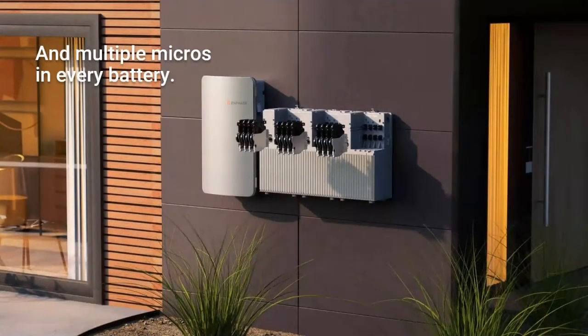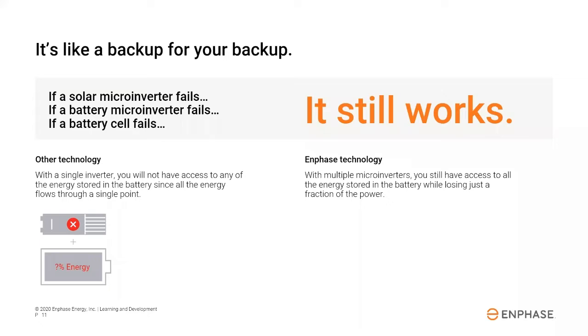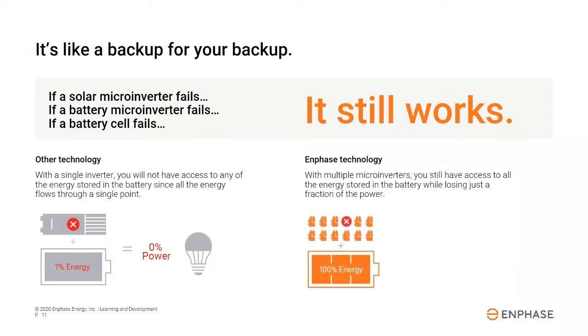It was natural for Enphase to use the same microinverter technology in the battery storage system. As with solar, the use of microinverters and distributed architecture in the battery units provides redundancy and improves the reliability of the system, ensuring that the owner has backup power when they need it most. Typical battery storage systems often have a single inverter, so a failure of that inverter would result in total system failure. An Enphase storage system will normally have at least 12 microinverters integrated with 3 or more battery units. A failure of 1 micro or 1 battery won't disable the entire system, but rather the power output will be slightly reduced until the microinverter is replaced. For example, if 1 of 12 micros fails, the battery will still be able to deliver 92% of its rated power. A battery with microinverter technology is like having a backup for your backup.